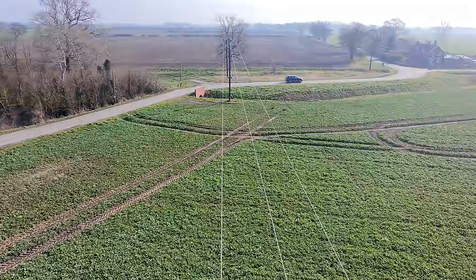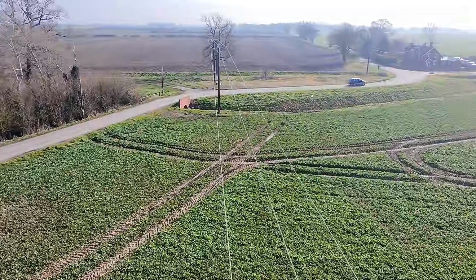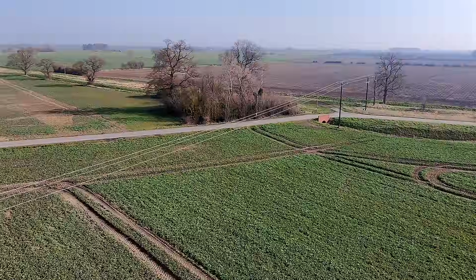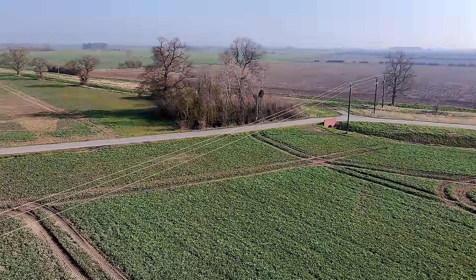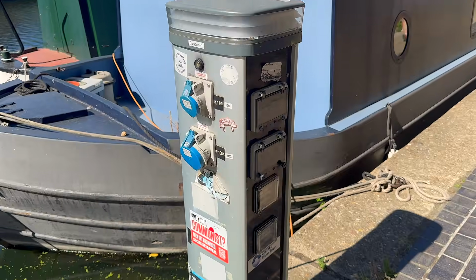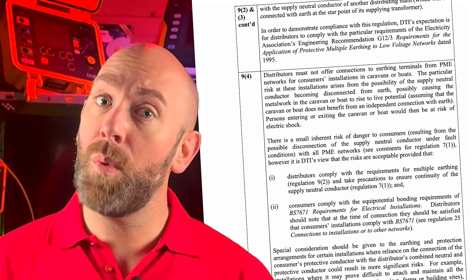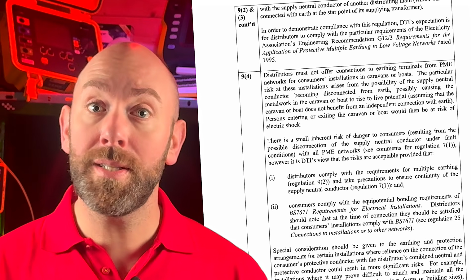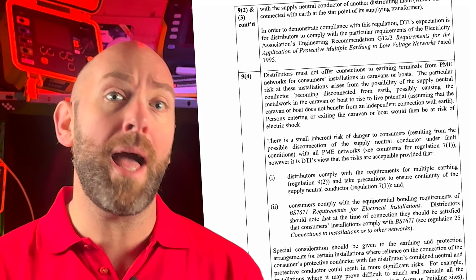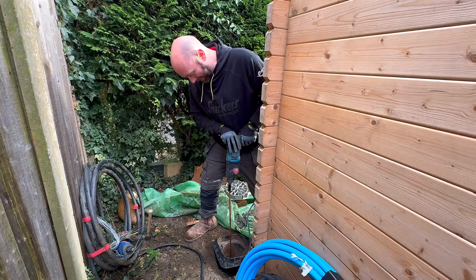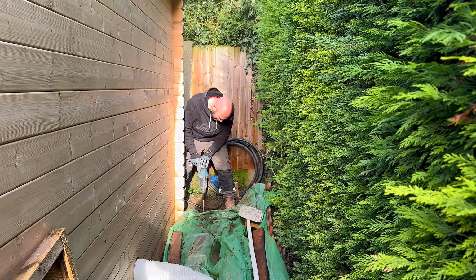A TT system is used where the distributor cannot guarantee the continuity of a protective conductor. That might be because the supply is delivered by an overhead line, or because of the location: construction sites, caravan parks, marinas, temporary supplies. In these situations, the Electricity Safety, Quality and Continuity Regulations do not allow a PME supply to be used. So the supplier does not give you an earth. That responsibility sits with the consumer, and the way the consumer provides the earth is by installing an earth electrode.